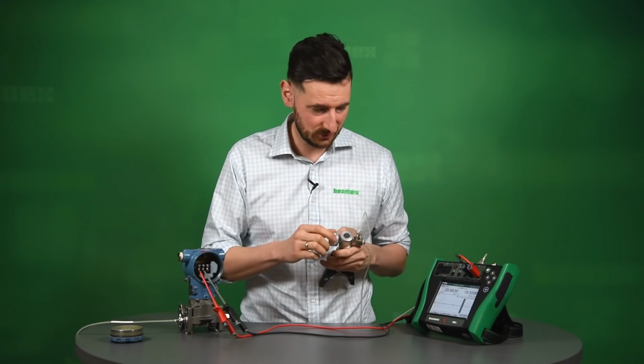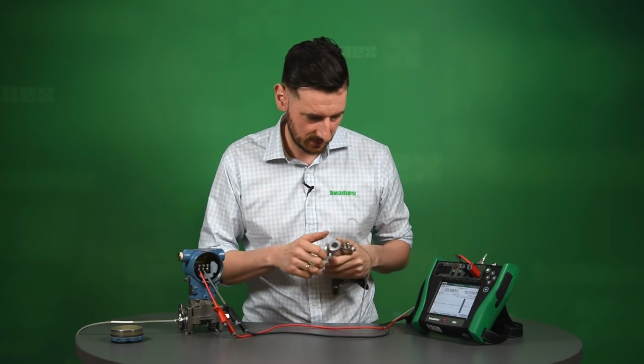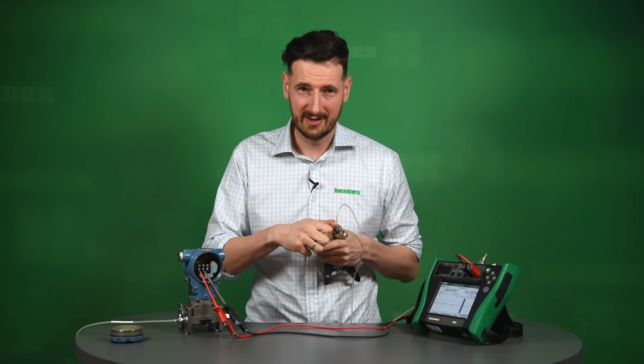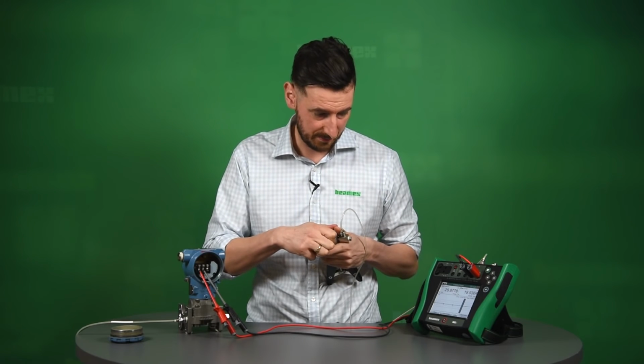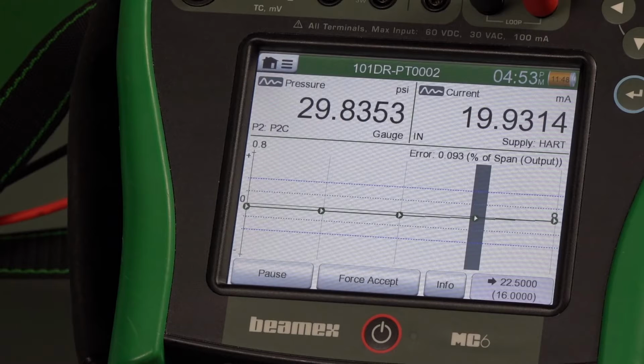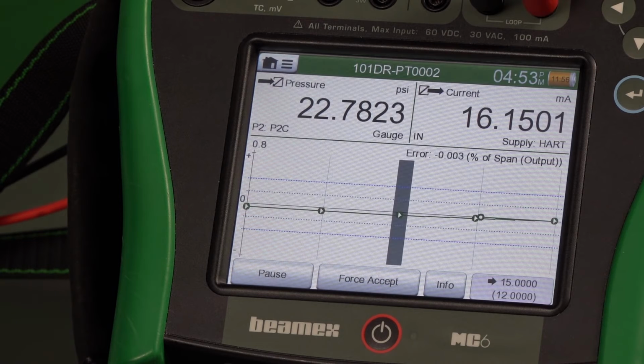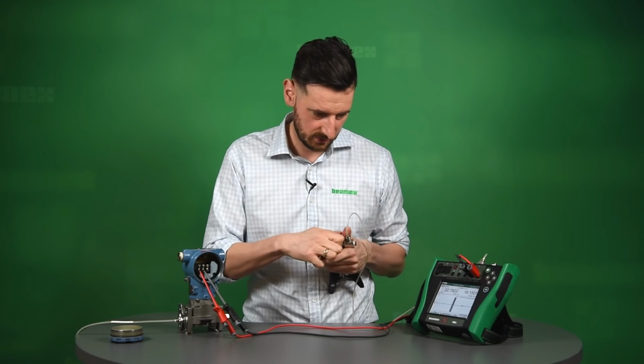We're at 30 and 20 milliamps. And right now we have to go down. So 22.5 is our next point going down. So that's what we're trying to do. Again, the same as for as found, we need to be rather careful going down. We want to make sure we don't drop too low. We would rather want to have a nice hysteresis, make sure the two are aligned going up and down. So that's fine, that's looking good.